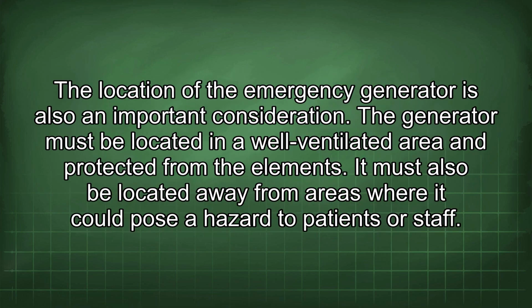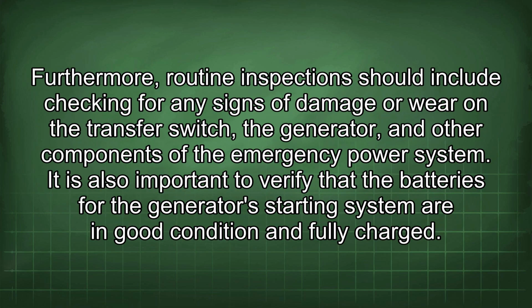The location of the emergency generator is also an important consideration. The generator must be located in a well-ventilated area and protected from the elements. It must also be located away from areas where it could pose a hazard to patients or staff. Furthermore, routine inspection should include checking for any signs of damage or wear on the transfer switch, the generator, and other components of the emergency power system.